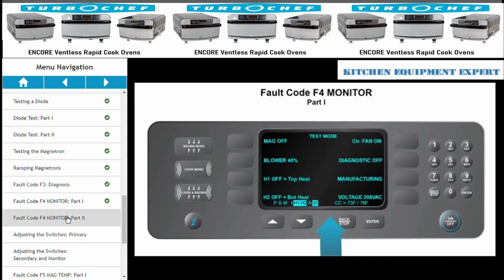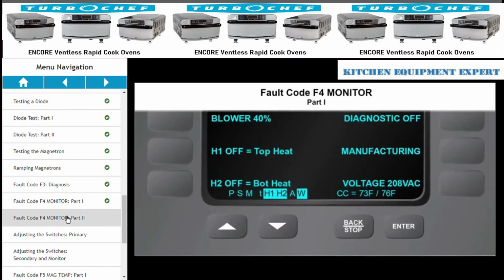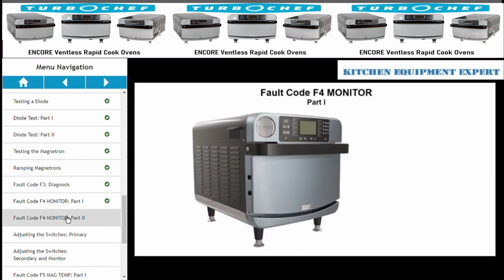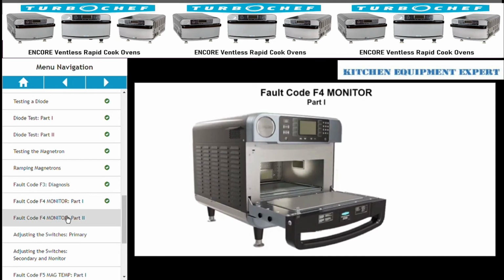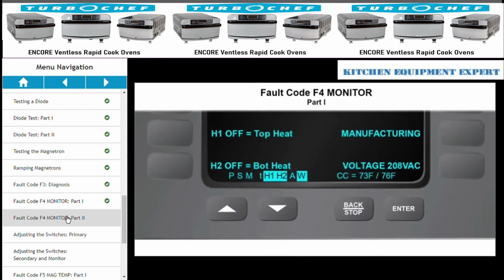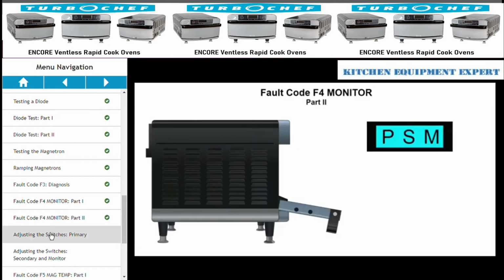Across the bottom of the display are the letters P, S, and M. When a letter is highlighted, it means that the controller is seeing that the switch is open. Start with the door closed and open it slowly. As the switch is open, the letters will highlight in order P, S, M. Now, close the door slowly and watch the highlights go out in order M, S, P.